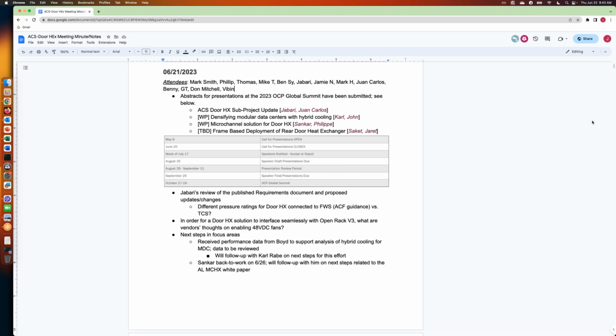Yeah, I think with the TCS, correct me if I'm missing your point here, Juan Carlos, but what I took away from that is that between the door heat exchanger and the cold plate, I don't want to use the term weakest link, but the component that's probably going to be more pressure sensitive is going to be the cold plate. So if the cold plate is more sensitive to pressure in the TCS, then maybe the pressure guidance needs to be defined by the cold plate and not the door heat exchanger.